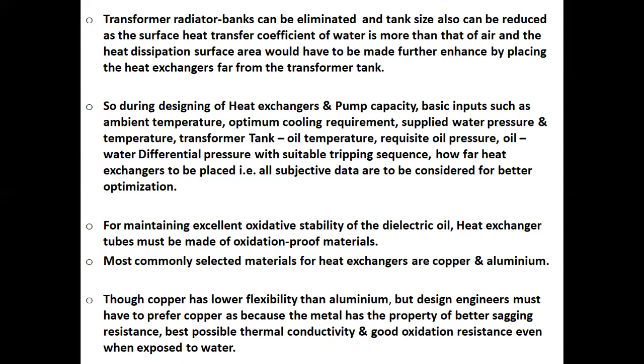That is better system optimization, cooling system optimization. For maintaining excellent oxidative stability of the dielectric oil, heat exchanger tubes must be made of oxidation-proof materials. Most commonly selected materials for heat exchangers are copper and aluminum.